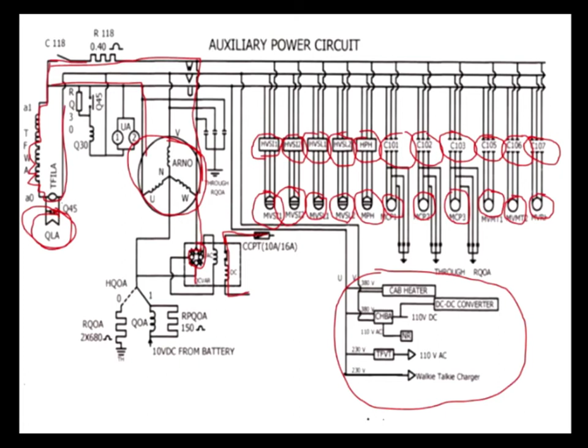And this auxiliary power circuit is protected by an overcurrent relay called QLA, which is set at 1400 amps in WAG5 and WM4, and this QLA is set at 2000 amps in WAG7 and WAP4 locos. So this QLA protects auxiliary power circuit from overcurrent in case of any short circuit.